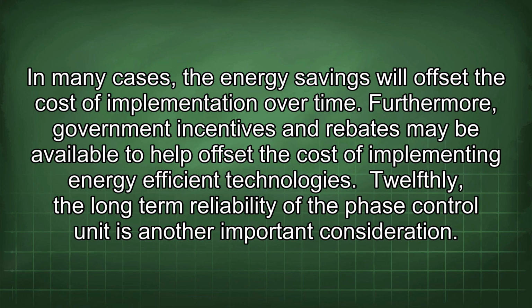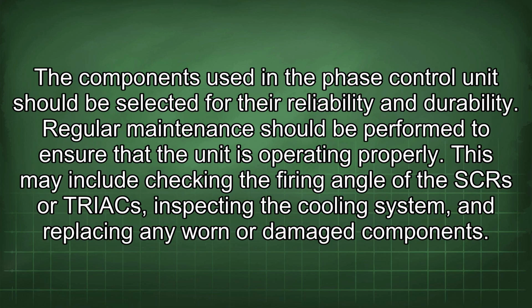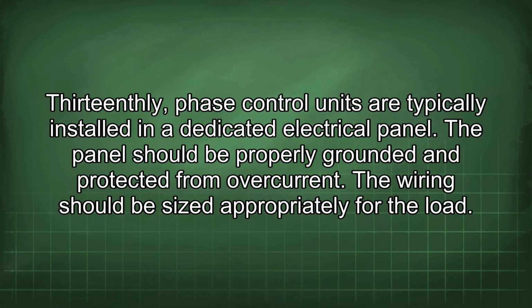12thly, the long-term reliability of the phase control unit is another important consideration. The components used in the phase control unit should be selected for their reliability and durability. Regular maintenance should be performed to ensure that the unit is operating properly. This may include checking the firing angle of the SCR or TRIACs, inspecting the cooling system, and replacing any worn or damaged components.